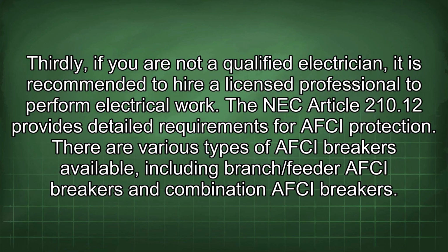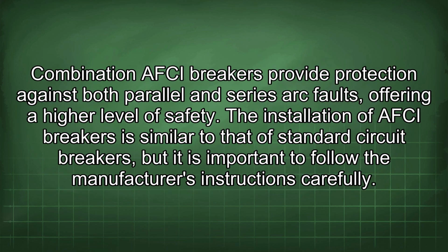The NEC Article 210.12 provides detailed requirements for AFCI protection. There are various types of AFCI breakers available, including branch/feeder AFCI breakers and combination AFCI breakers. Combination AFCI breakers provide protection against both parallel and series arc faults, offering a high level of safety.